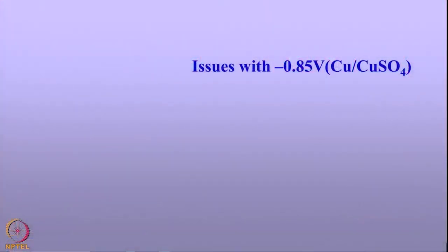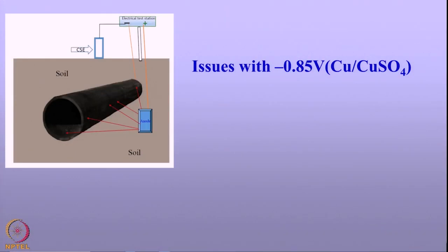Let us look at the merits and demerits of each criterion. The first criterion is minus 0.85 volt pipe-to-soil potential measured with respect to the copper/copper sulfate electrode. This criterion is a simple method, very versatile, and you can measure the potential at any time — in fact, it can be measured online. However, the main problem arises from the fact that the measured potential may not actually correspond to the true polarized potential of the pipeline.